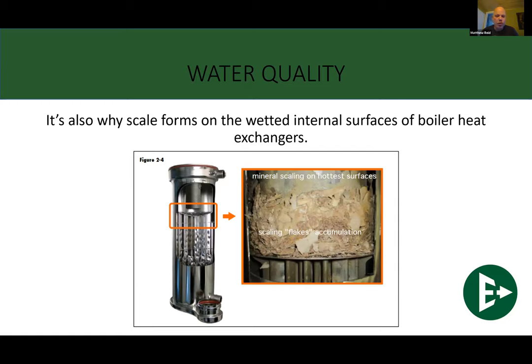So scale is going to happen on, I picked this picture for a reason. Number one, it shows the inside of a fire tube heat exchanger completely covered in scale. So these people that say that they are self-cleaning, this is what I'm talking about. You've got to clean them up yourselves, not just the burners, but you've got to do a flushing and make sure your water quality is taken care of. So scale happens. As that water heats up, the salts come out of the solution, your hardness comes out of solution, and it sticks to metal surfaces. It loves metal surfaces. So it sticks to that, and that creates a scale buildup.